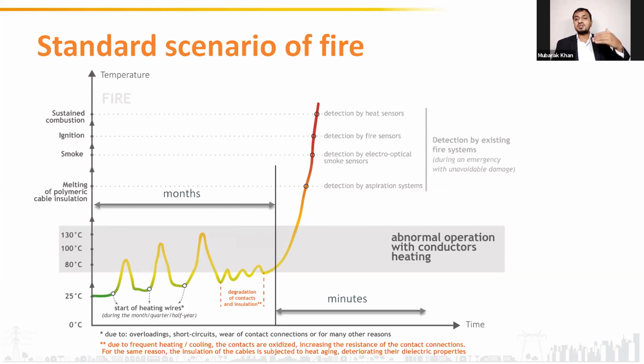When the temperature of the joint starts to increase, it will cross 80, 100, 130. It will reach around 200 to 250 degrees Celsius, where the polymeric insulation will start to melt. At that time, after some time, there will be smoke. At further temperatures, there will be ignition and sustained combustion. In this particular scenario, if there is a fire alarm system already installed inside the panel or in the control room, that fire alarm will get activated. When the fire catches, at that time, the fire alarm will get activated.